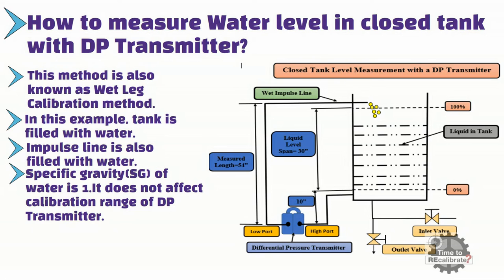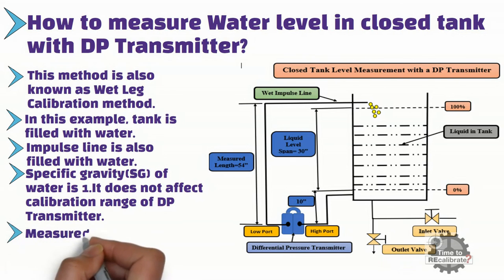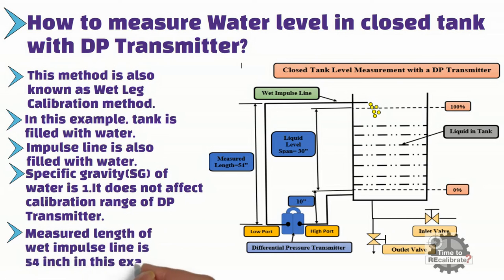As you can see from the picture, the wet impulse line is connected with the low port of the DP transmitter, and this impulse line is filled with water. The vertical height of the wet impulse line is also very important in closed tank level measurement, so measure the height of the wet impulse line very carefully. In this example, the measured height of the impulse line is 54 inches. There is a 30-inch distance between the zero percent baseline and the 100% level. Now we are all set for calculation of the calibration range.